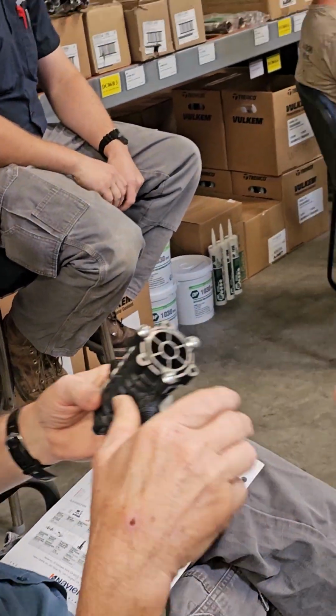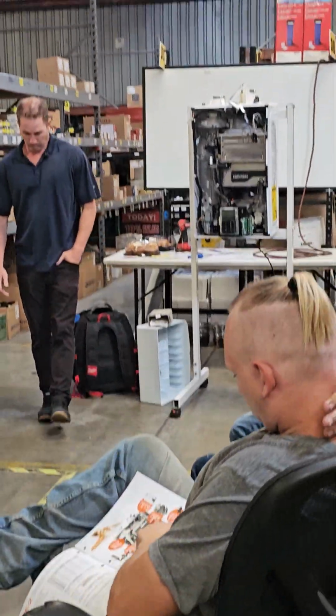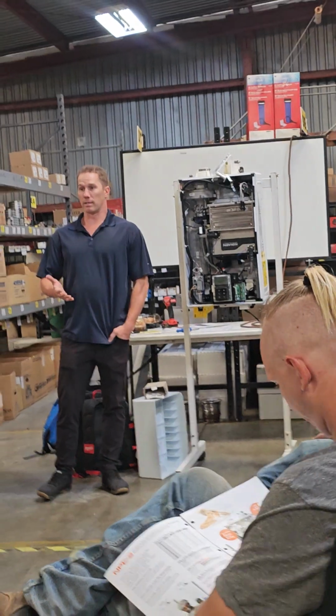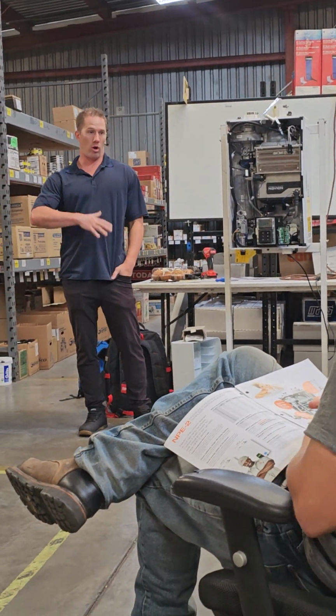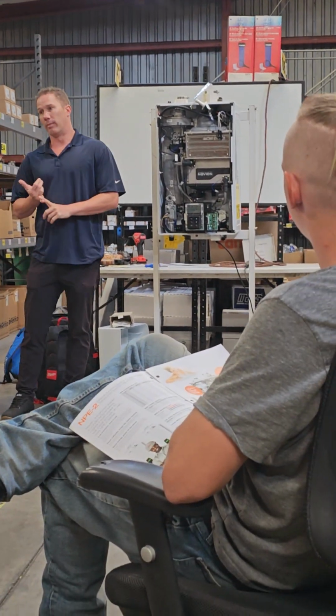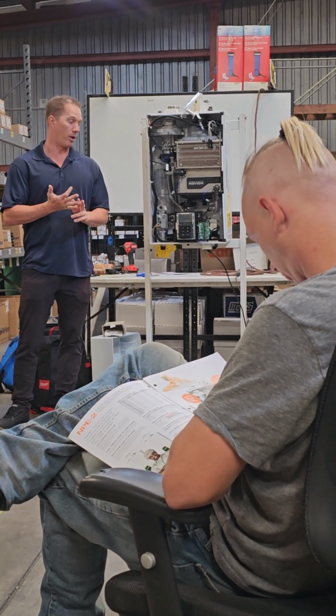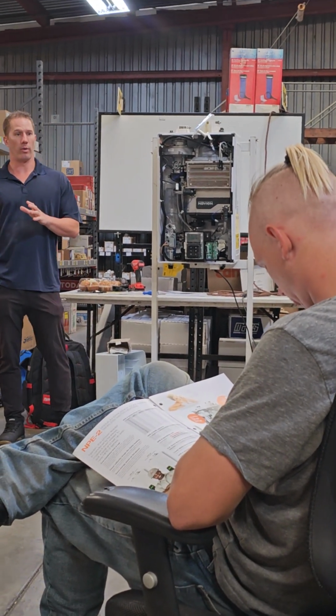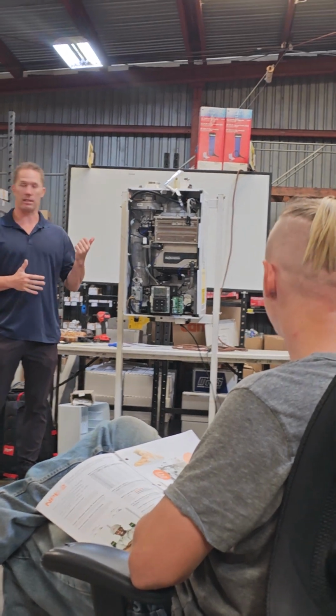Tankless water heaters need at least 0.5 GPMs of flow. If you put in a Grundfos one, I know guys say, I've been putting Grundfos ones in for years, they work great. They work great until they don't. If they don't open all the way, there gets some scale buildup in it, and if it doesn't open up all the way and get the full 0.5 GPMs, this thing will just never fire.